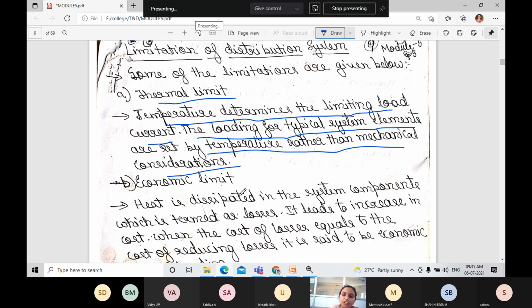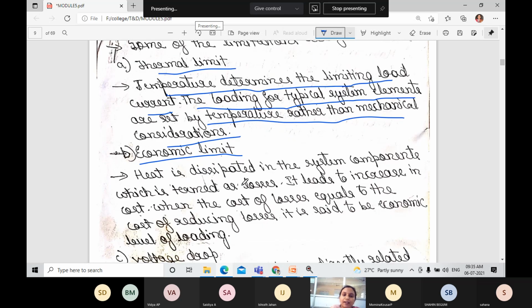For example, even a transformer, if you take a small device, will check the temperature. Next, economic limit: heat is dissipated in the system components, which is termed losses. It leads to an increase in cost. When the cost of losses equals the cost of reducing losses, it is said to be the economic level of loading. If we use capacitance or filters to reduce the harmonics, then the capacitor cost and the loss cost are similar. It should be balanced.